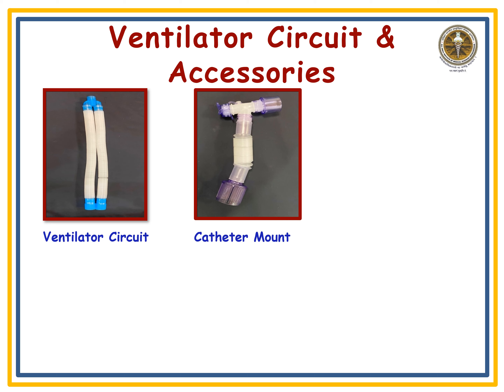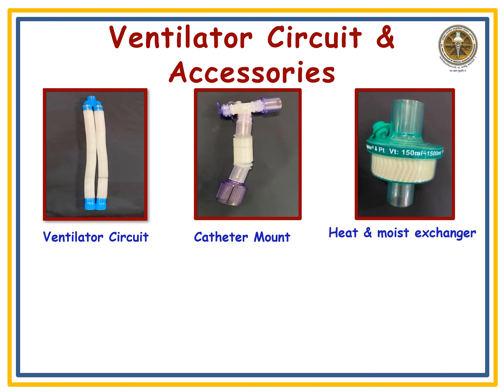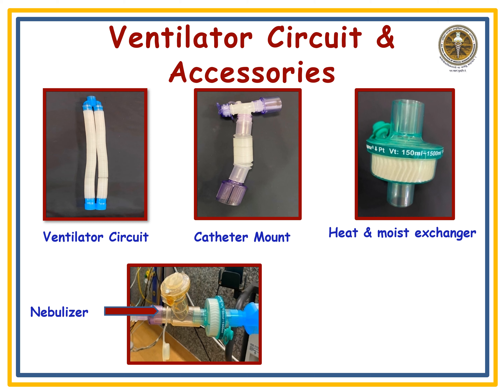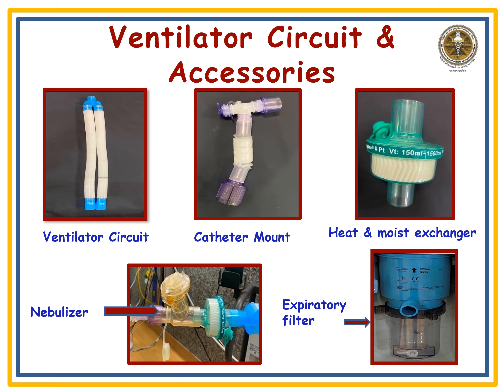We use two HME filters (heat and moisture exchanger or bacterial filter) in the circuit. A T-piece nebulizer or fogger is used in the closed circuit system. The expiratory filter is already fitted in the assembling unit of the ventilator.